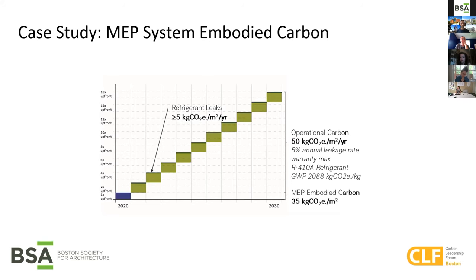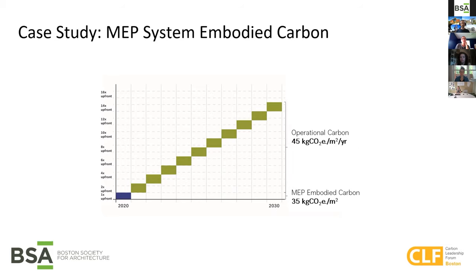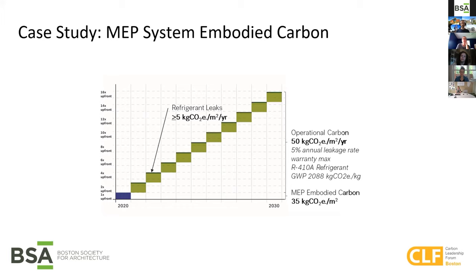Toggling between the two, we can see a bit once we add in refrigerant leaks, using an annual leakage rate of 5%. Here's operational carbon before refrigerant leaks, and here's operational carbon once we count refrigerant leaks. This project used R410A with an initial charge of about 1,500 pounds, which has a very high global warming potential of 2088.